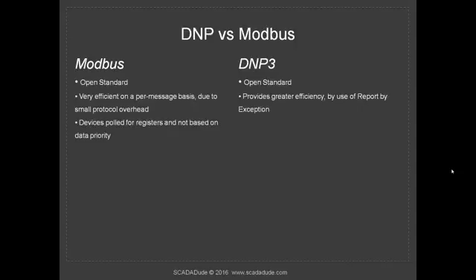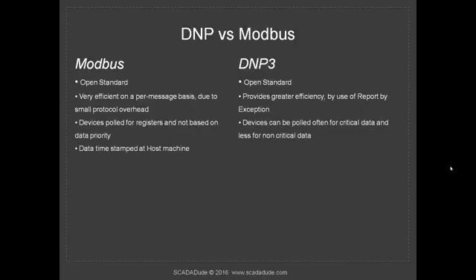In Modbus we poll the registers not by the priority of the data. On DNP3 they've got these different classes and you put different data in different classes, and that's how you poll the data. So you can poll the more critical data more often and the non-critical less often.